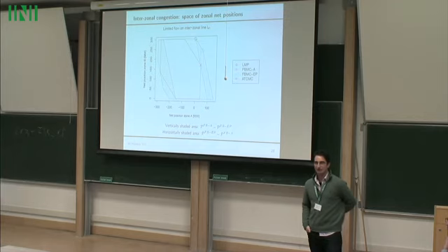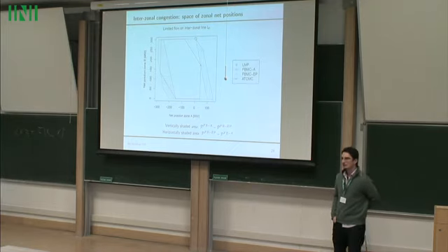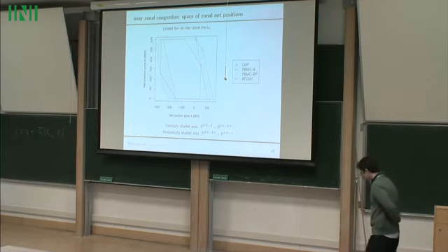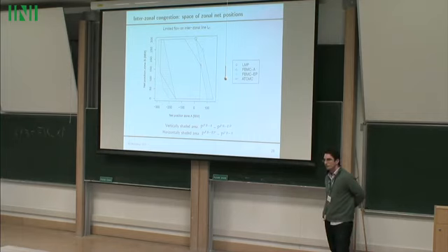But I don't know how we find zones, because in flow-based, the critical branches could change over time. The hubs are defined, so you have to select a hub to put the bids, but then you use all the model of the full network. Depending on the hours, depending on wind or no wind, the critical branches are changing. If you use PTDFs, you're stuck. So flow-based is not exactly a zonal setup. There is a kind of fuzziness. Of course, we have some hubs, but the critical lines are changing over time.